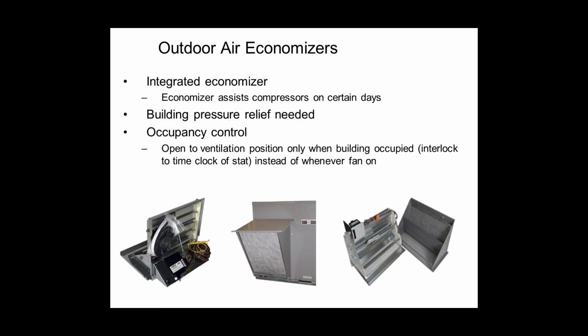The one that gets everybody, and this is not even new on the 2015 code. This came in the 2012 code. It just wasn't being policed until more recently. The economizer also does double duty and serves as my minimum mechanical ventilation code intake, right? So I need 10, 12, 15, 30% outside air by code for whatever my project needs. I typically bring that in through the economizer damper. Let's just say 30% for argument. And then if I have an economizer cooling day, I modulate between 30 and 100% open. But that first 30% comes on whenever the building's occupied, right, to bring fresh air in for the people.